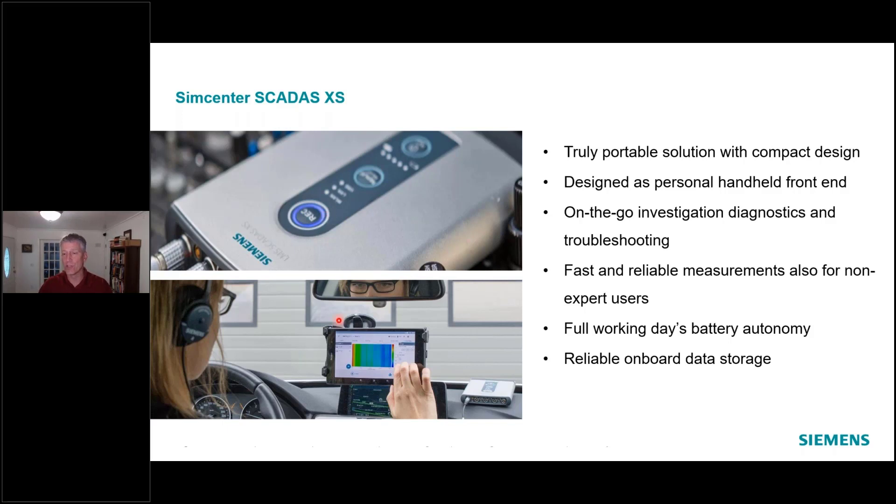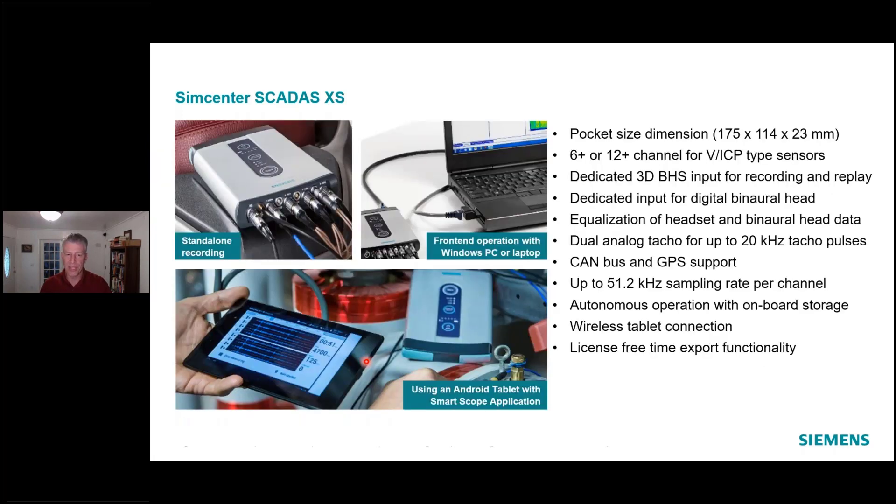Most of our customers really enjoy the Android tablet application — the scope app — where you can get all different kinds of views: overall levels, the levels for a given channel, change configurations, calibrate things, look at waterfalls, color maps — all while running that SCADAS XS hardware. Think of it as a very fancy remote control.